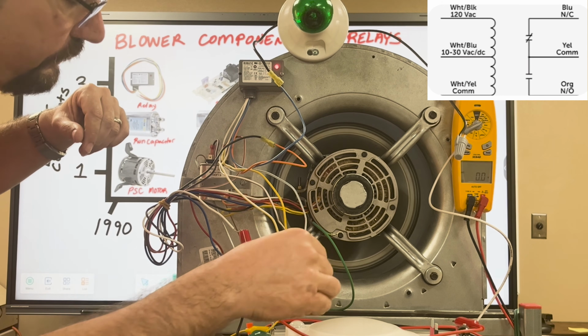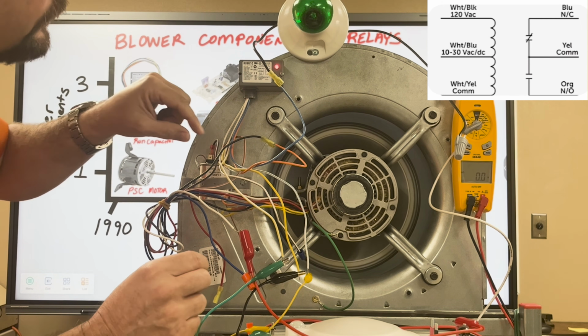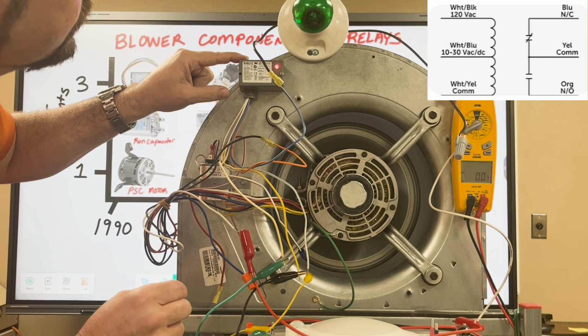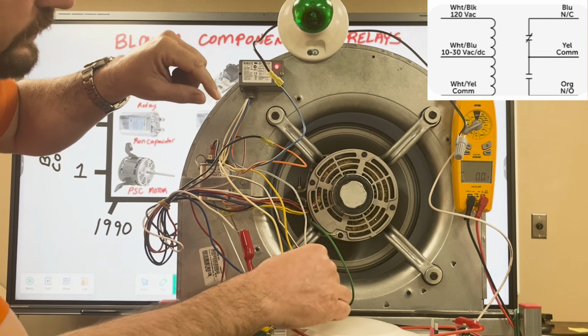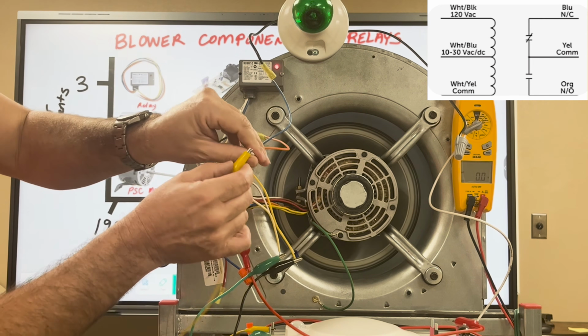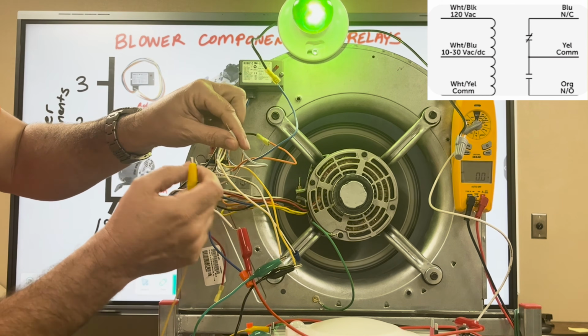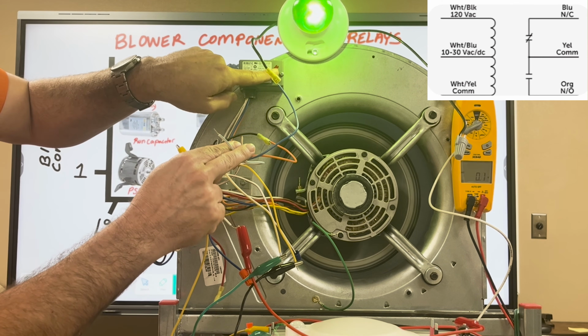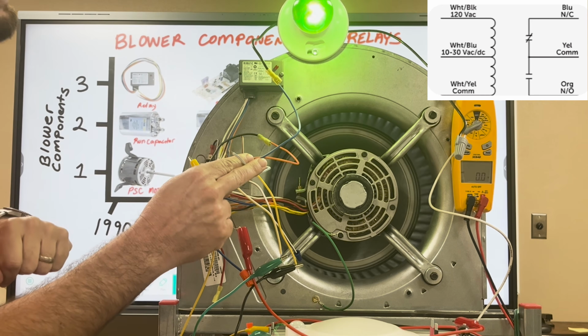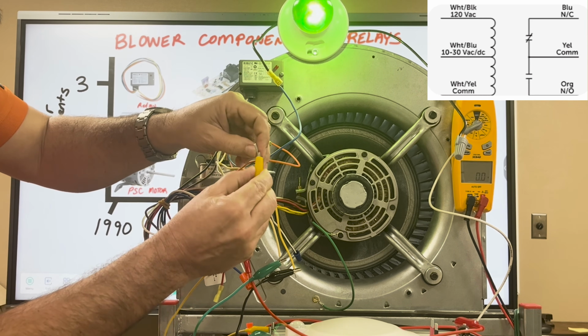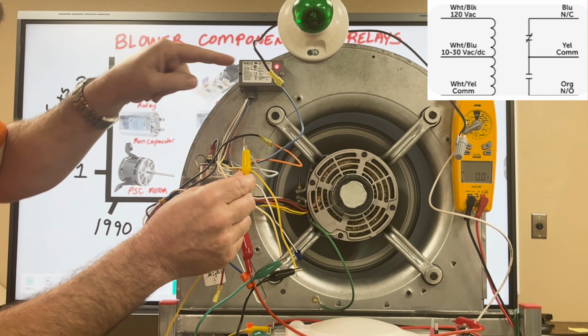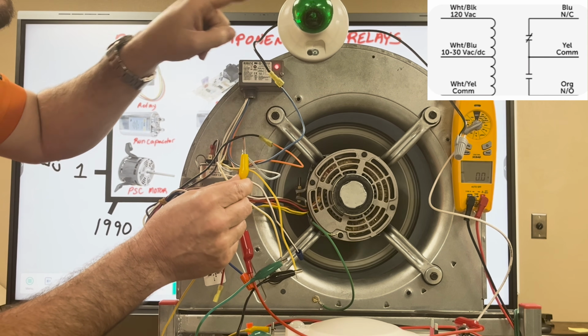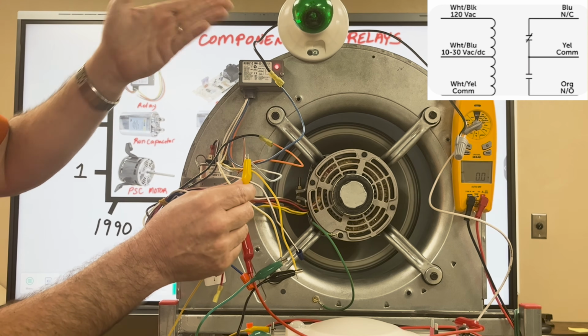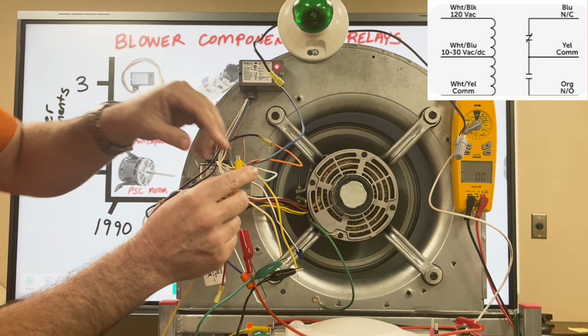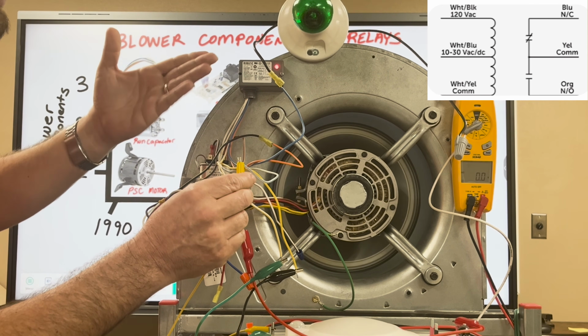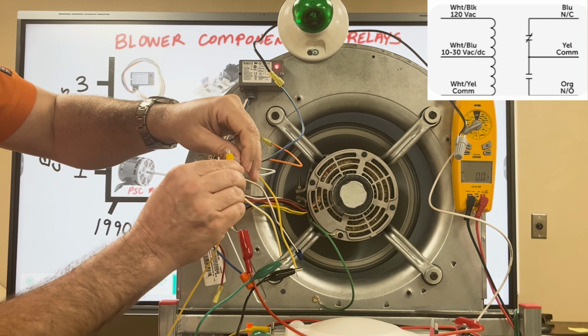So we want to go to the white/blue wire right here. And we're going to go ahead and disconnect that. And this removes 24 volts. You see the RIB relay now has the light off, the motor is off, and the green light bulb is on. We'll simply connect coil voltage again. The motor comes back on, the coil voltage indicator is there, and my normally closed load turns off. So this is an example of how to wire 2 loads to this relay, which is a single pole, double throw.